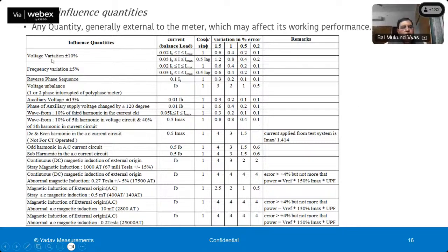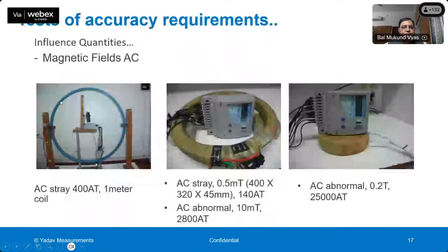Similar table is there in all metering standards. This picture is actually showing how magnetic field influence is tested. In the first picture, there is a magnetic coil of 1 meter, and the meter is kept at the center. Current is passed through this coil, and an AC magnetic field is created at the center of the coil, and the meter's accuracy is tested. Similarly, you can see in the second and third, the magnetic coils are there, and the meter's accuracy is being tested at different magnetic fields, 0.5 millitesla, 0.2 Tesla, and so on.